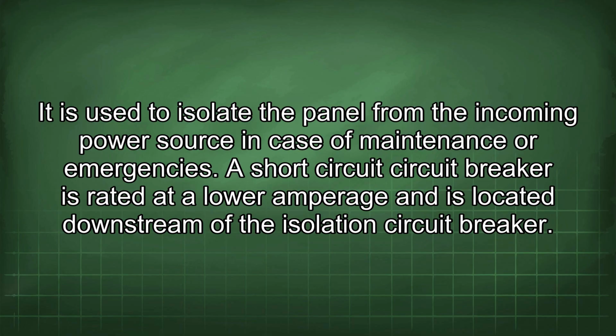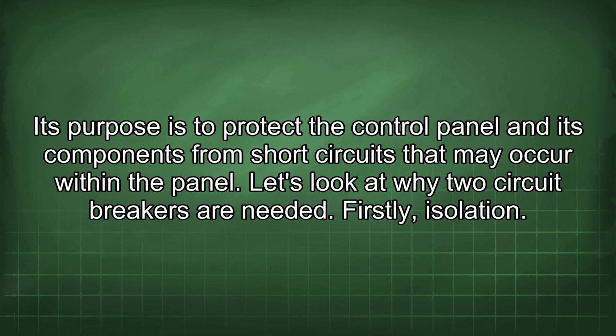A short circuit circuit breaker is rated at a lower amperage and is located downstream of the isolation circuit breaker. Its purpose is to protect the control panel and its components from short circuits that may occur within the panel. Let's look at why two circuit breakers are needed.